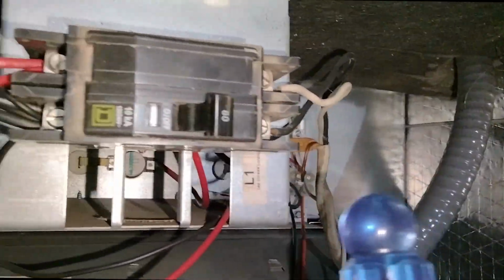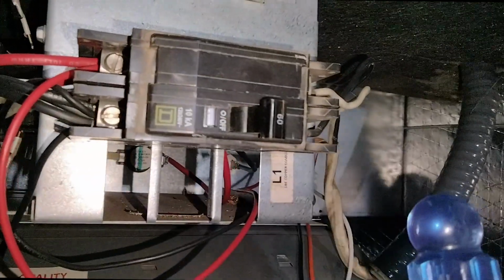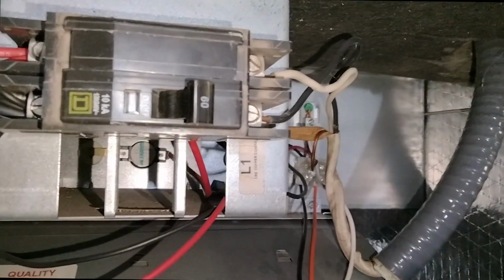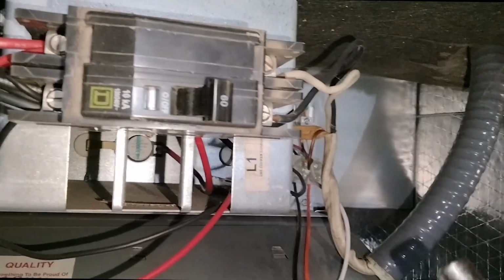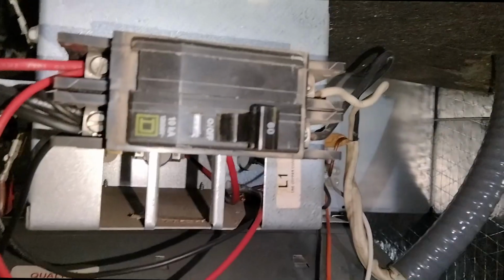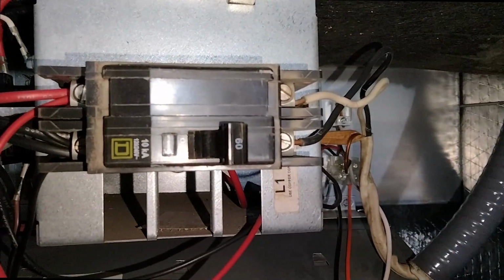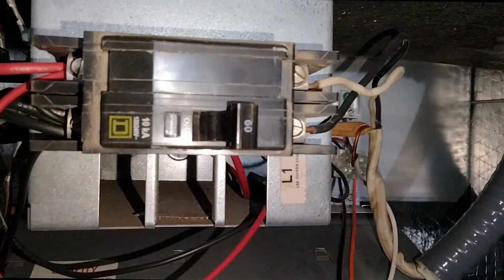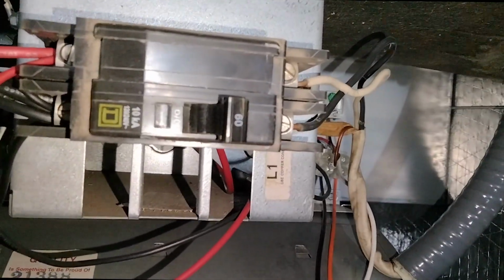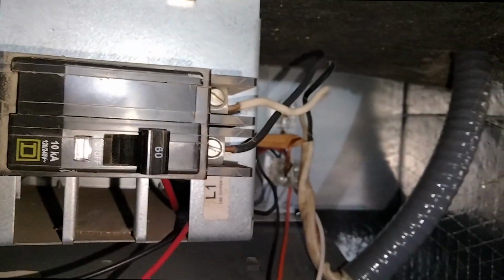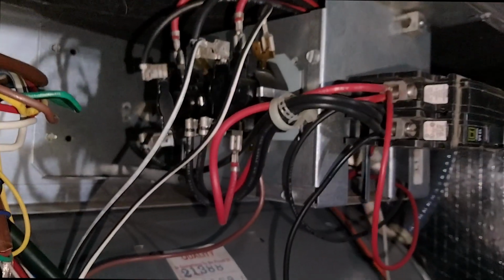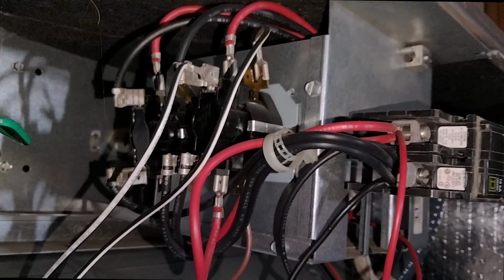Check continuity on your breaker. And of course, you can check continuity here if you're just wanting to make sure it's making good contacts in the center. And of course, once you flip your machine on in order to call for heating or cooling, you're going to flip these on to make sure that you are in fact getting your 240 volts in and out, ruling power out, ruling relays out, sequencers, and of course our transformer, which would be the more obvious one.